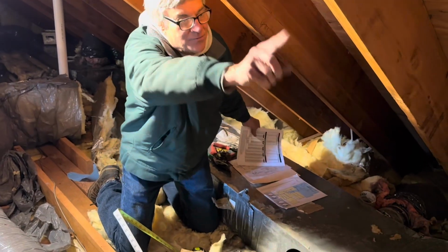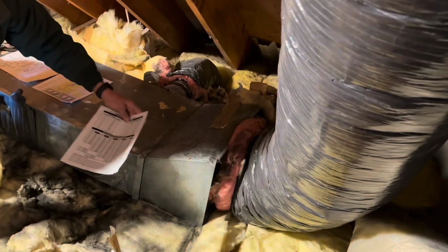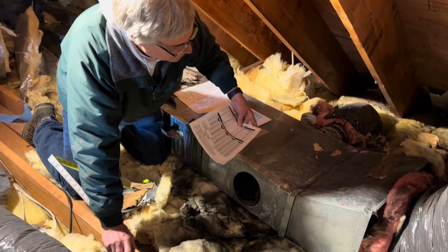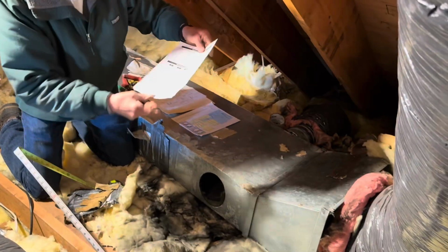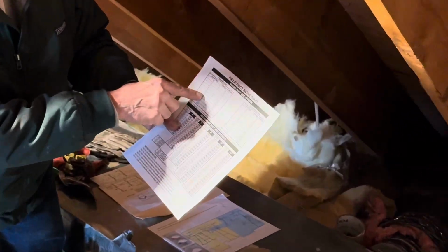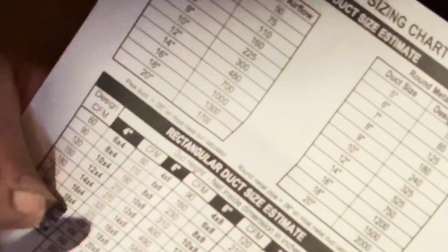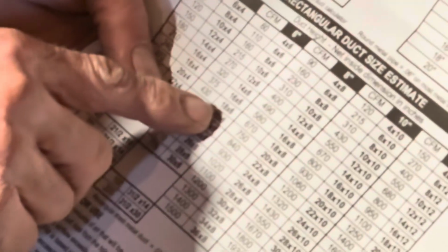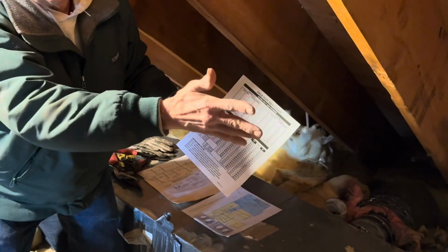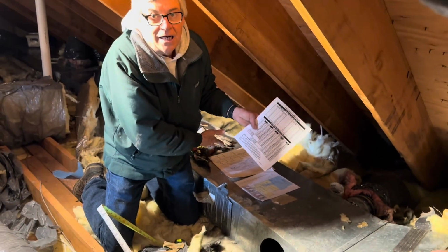The other thing we look at is flex duct. We have this flex duct coming into this metal duct, which is lined, which is reduced to 6 by 18. The flexible duct is 12 inches, which has the maximum capacity to supply 480 cubic feet a minute of air. And then when we go to our 6 by 18, we have 430. So this flex duct is supplying enough air to fill this lined duct.